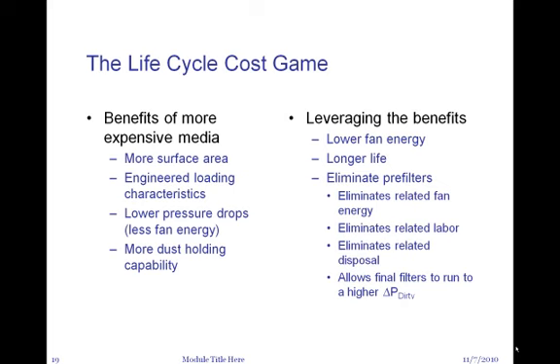But if the final filters can hold two or three or four times as much dust, maybe get rid of the pre-filters and just let them load a little faster. Because if you get rid of the pre-filters, you've eliminated a fixed pressure drop in the system forever. Assuming the final filters are rated for it — and most of them, that's part of what you get for the money — most can take more static. You can actually run that final filter to the pressure drop you used to run the pre-filter plus final filter to. So it tends to make the life cycle longer, and you can leverage those things to actually gain some benefits.